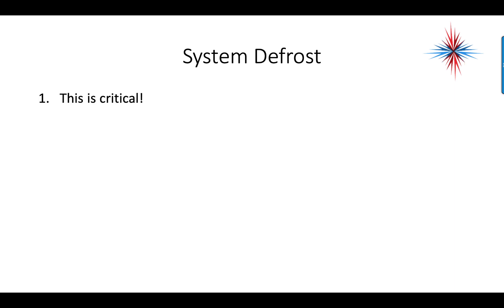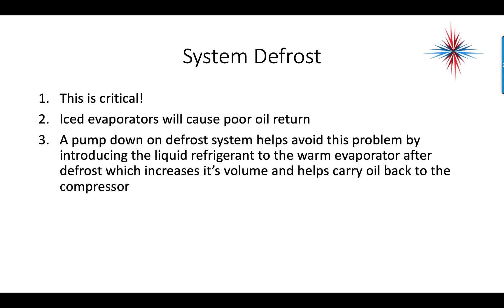System defrost is critical for low temperature refrigeration systems. Iced evaporators cause very poor oil return. A pump-down on the defrost system helps avoid this problem by introducing liquid refrigerant to the warm evaporator after defrost, which increases its volume and helps carry oil back to the compressor.